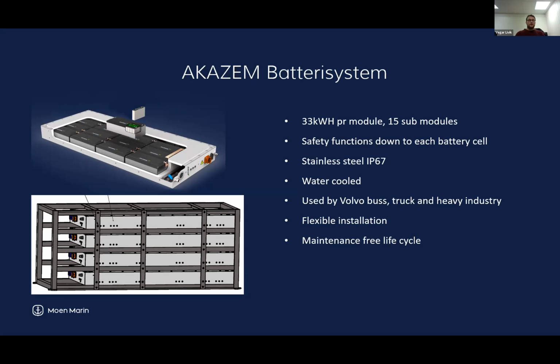These battery modules operate on the same life cycle terms as the Norwegian NORA standard, which is 10 years. But from vessels we delivered two years ago, we're seeing the energy drop per cycle is lower than expected. So with some certainty, we can now say the life expectancy until 70% of installed capacity is at least 15 years before you need to change the battery system. Even then, the rest of your system will be ready for a new battery system, so you can install the state of the art.